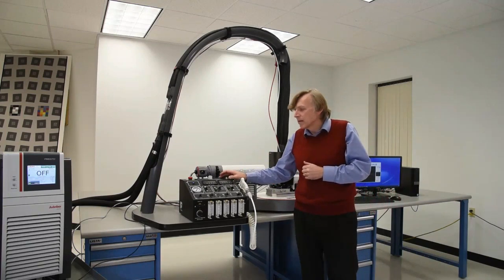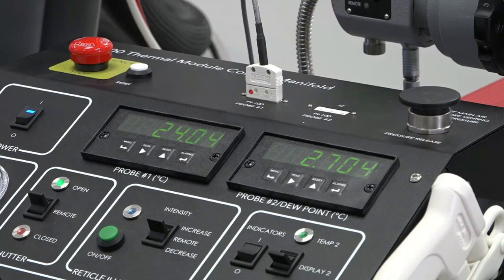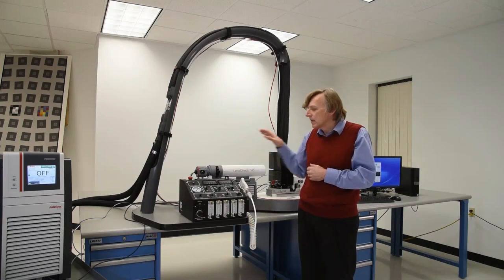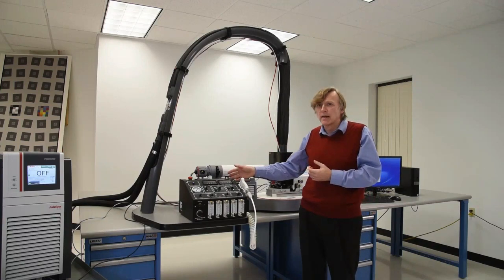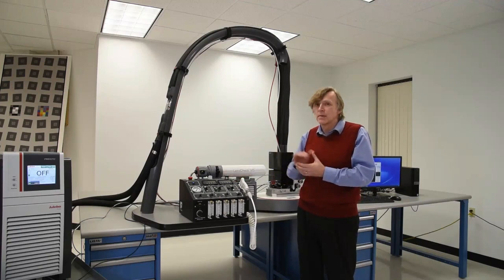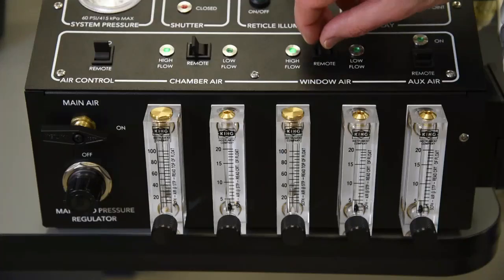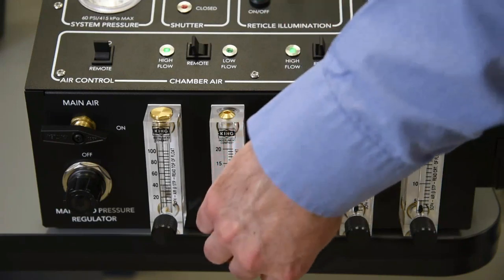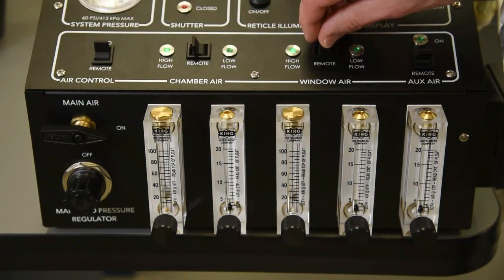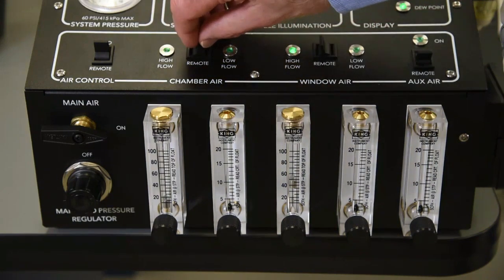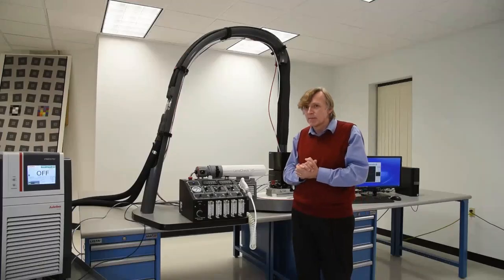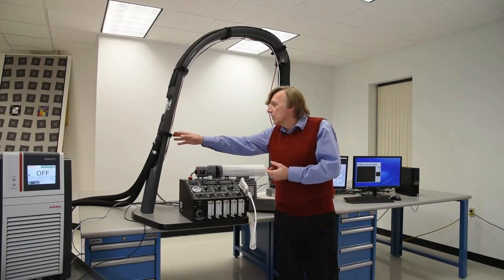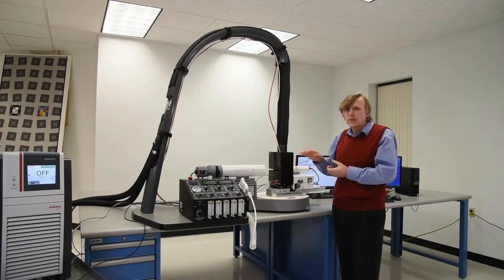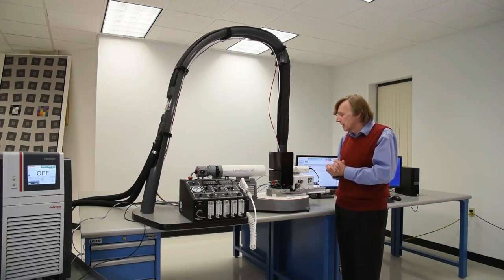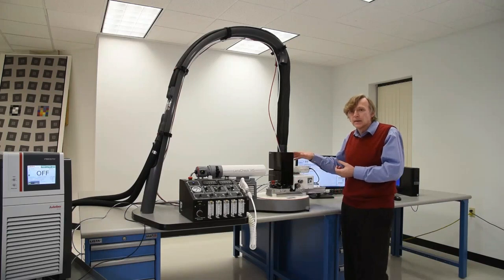That's where this module comes in. This is the CM1000 control manifold, and it performs several functions, but its main purpose is to regulate the flow of dry air into the thermal chamber. Customer-supplied dry air enters the manifold from the back. In our case, we're simply using a commercial two-column air dryer to reduce the dew point of the shop air to negative 40 degrees. These rotameters along the front panel incorporate needle valves that the user can set to predefined flow rates, and then a series of remotely controlled valves commanded by the Optikos 7 software turns the air onto specific channels at preset temperatures. The air flows out through these colored tubes and enters the chamber from above, where it is directed to where it is needed. In this way, we are able to maintain a dry atmosphere over the windows and around the lens under test.